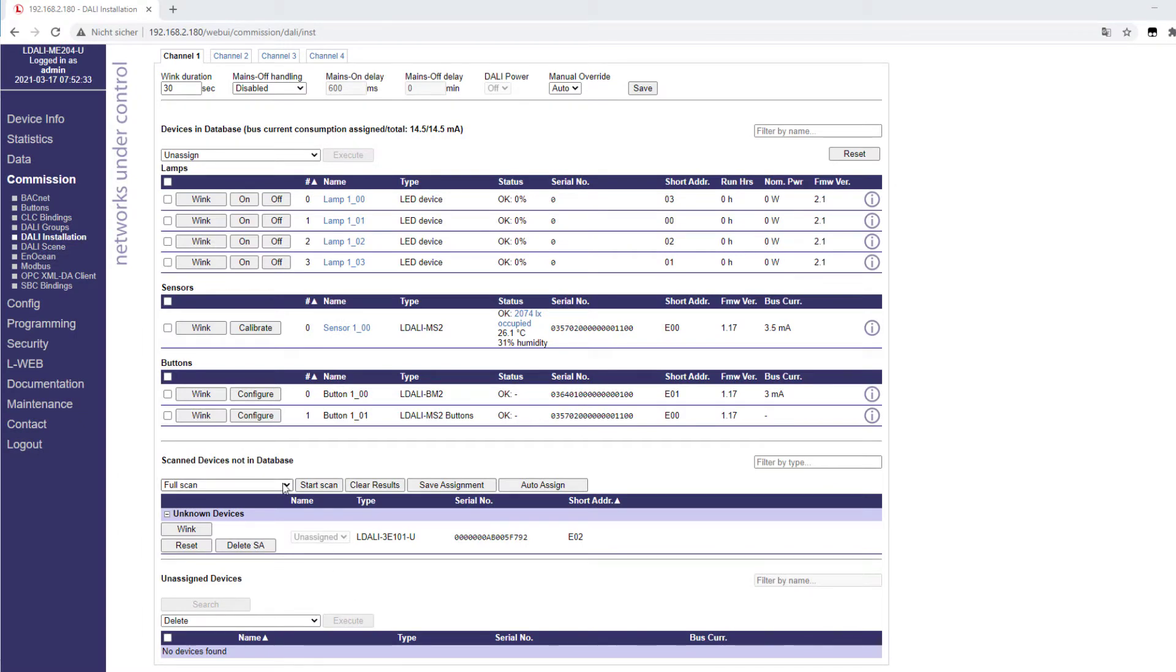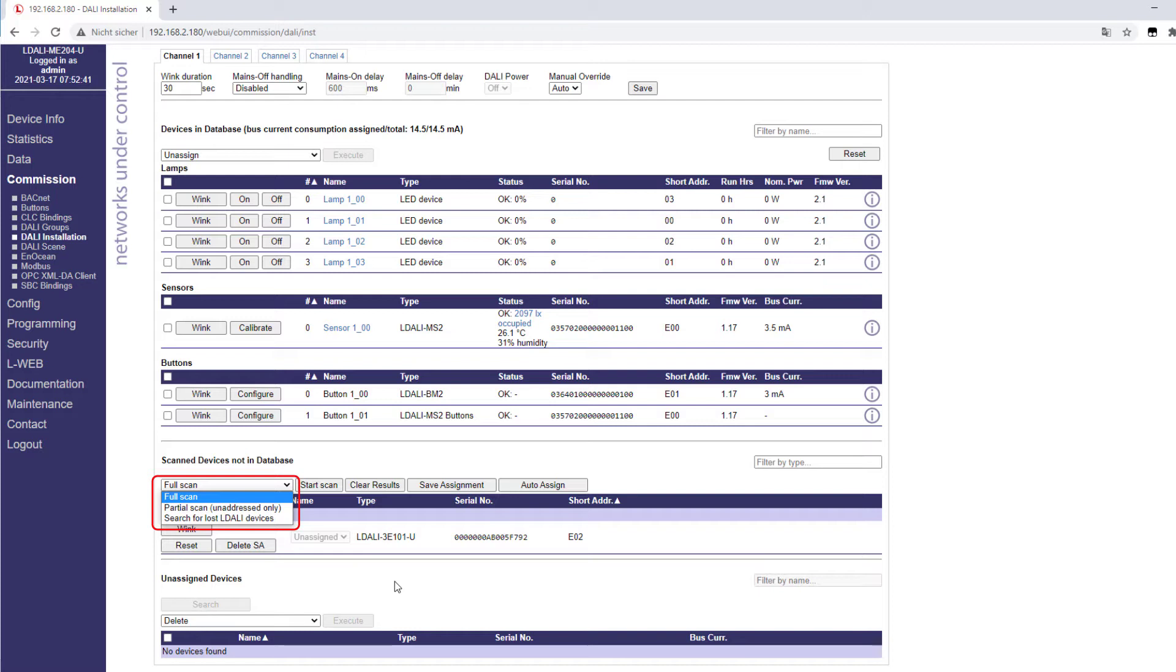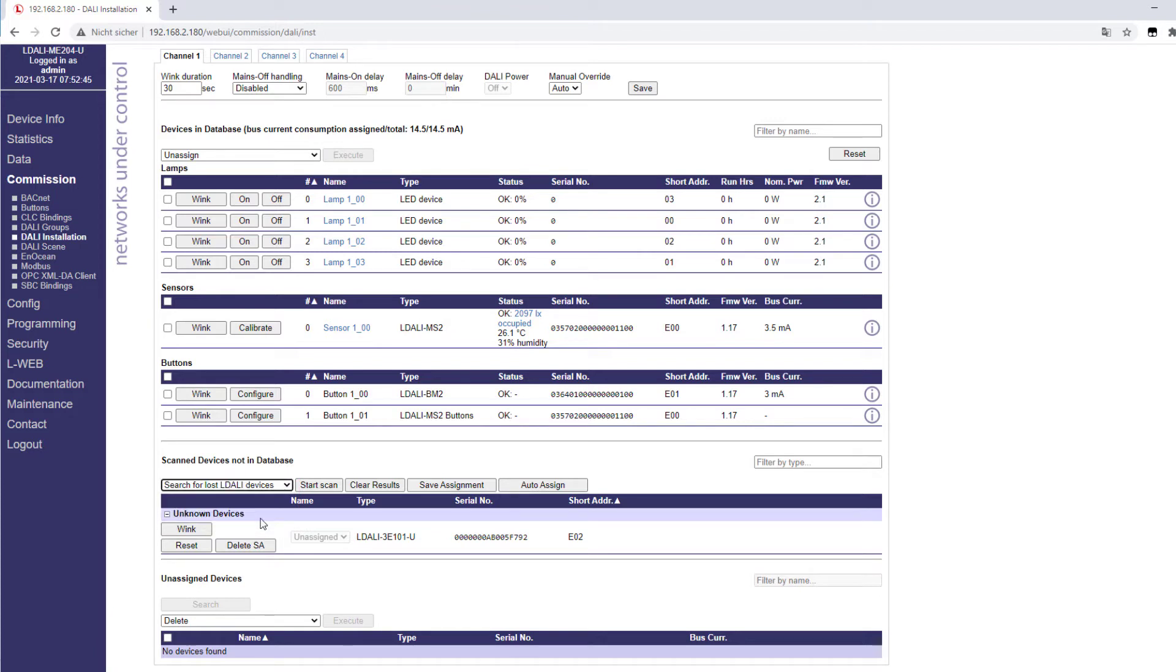In addition to the full scan, two new options have been added to the DALI scan. A partial scan only searches for unaddressed devices. This is useful if you want to add new devices to an existing installation, as it shortens the DALI scan considerably.